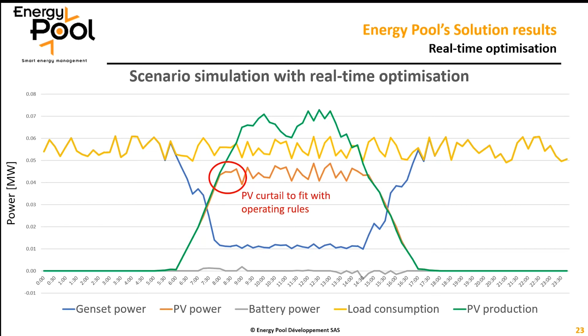Let's now add the forward-looking optimization. During nighttime, we still have no PV production, so the load is still covered by the genset power. At 5 a.m., the forward-looking optimization has the forecast that it will be a sunny day, so we will have a lot of PV production. It also receives information from the microgrid controller that the battery is full, so it calculates the optimized profile and says: if at 5 a.m. the battery starts to produce, we can shut off one genset.